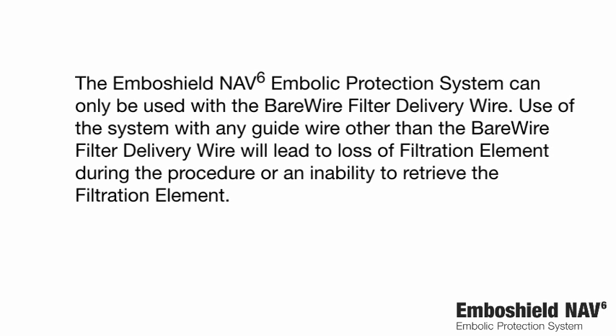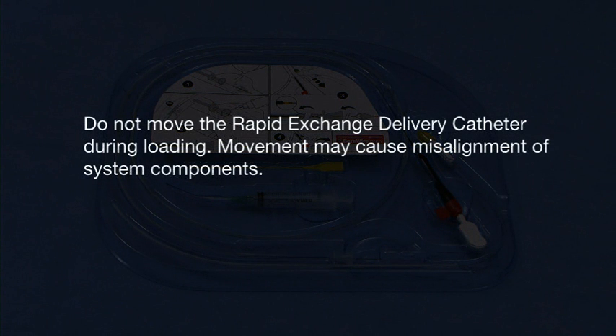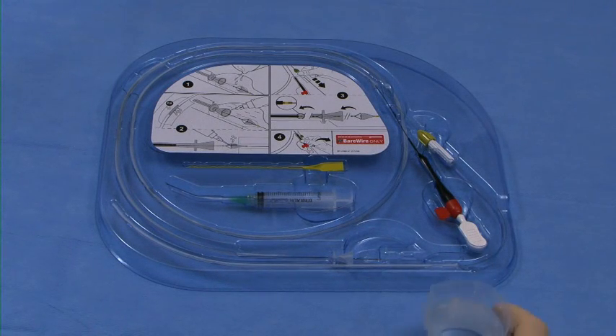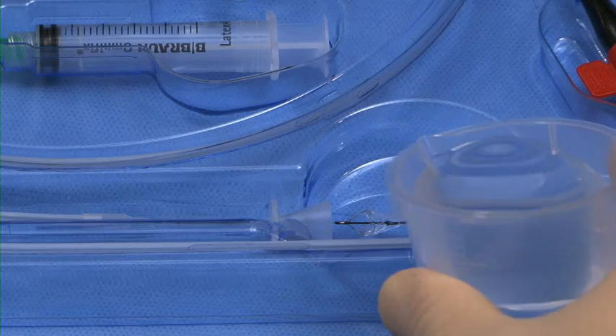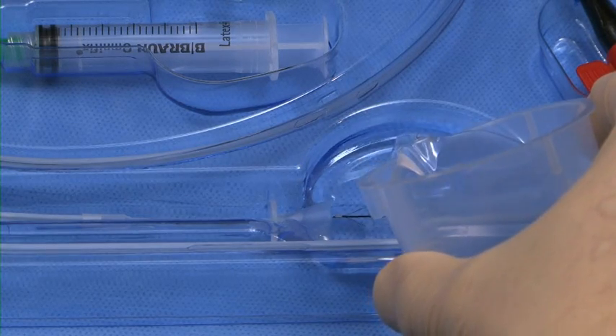The Emboshield NAV6 Embolic Protection System can only be used with the bare wire filter delivery wire. Use of the system with any guide wire other than the bare wire filter delivery wire will lead to loss of filtration element during the procedure or an inability to retrieve the filtration element. Do not move the rapid exchange delivery catheter during loading. Movement may cause misalignment of system components. Fill the recessed well area with heparinized normal saline until the filtration element is completely immersed.